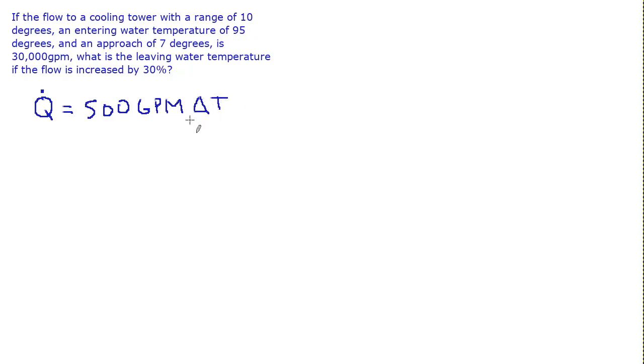If we set those equal, we could say GPM1 times delta T1 equals GPM2 times delta T2. And then we could solve from there where we know the ratio of the GPMs. GPM2 over GPM1 equals 1.3 because it increased by 30%, and that equals delta T1 over delta T2.